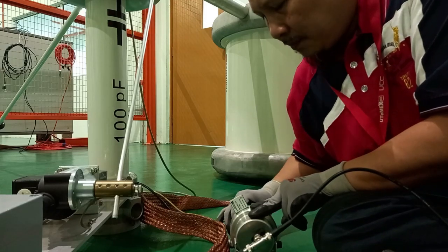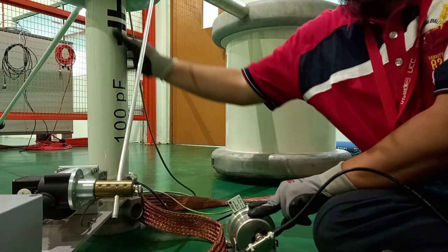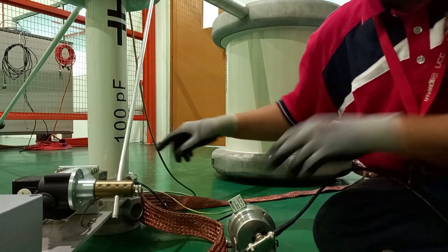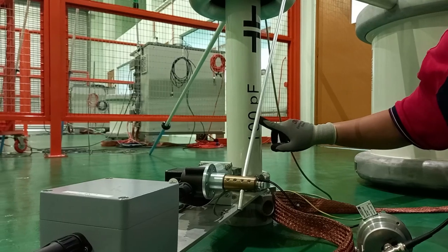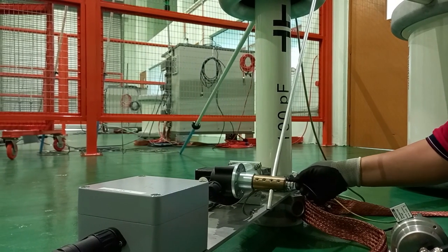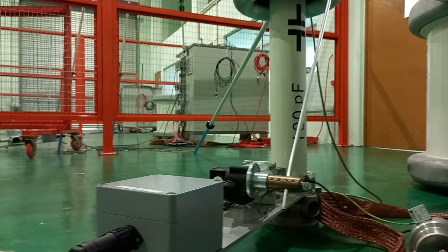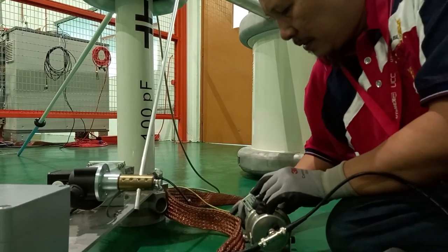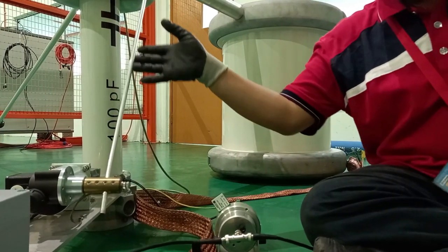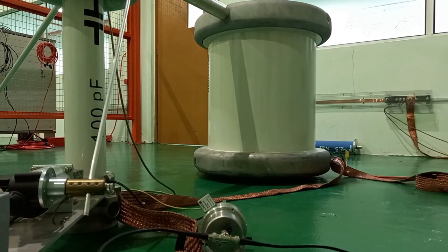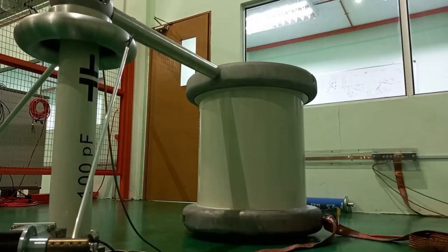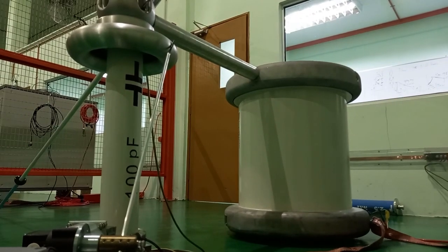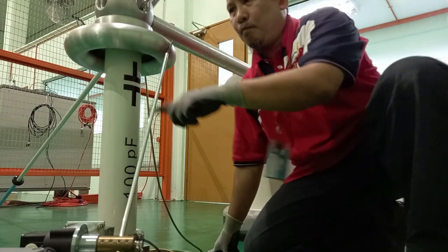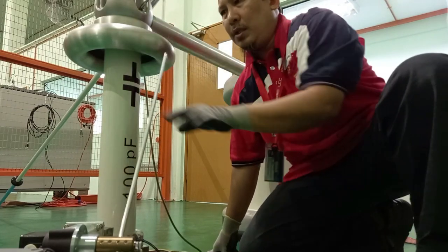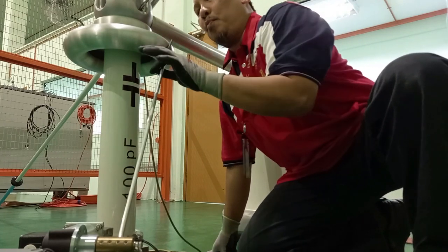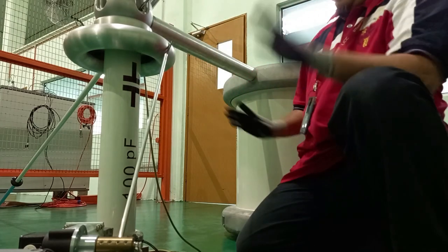And then please also double check at this side, I mean, the side that we connected from the big capacitor, 100 pico farad. Please ensure you also do a pulling test as well. Once we have done, again, double check this one. Again, please double check this earthing switch. The earthing switch must be properly touching our top electrode. Okay, now basically we have done.